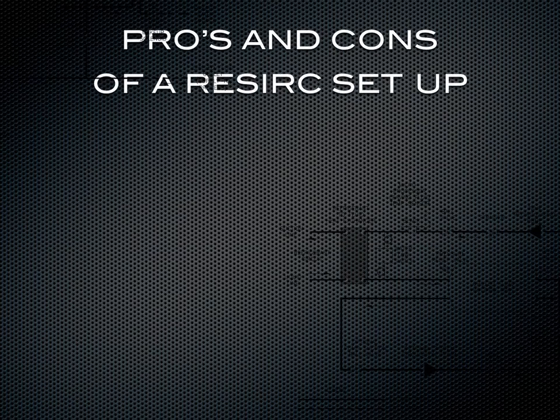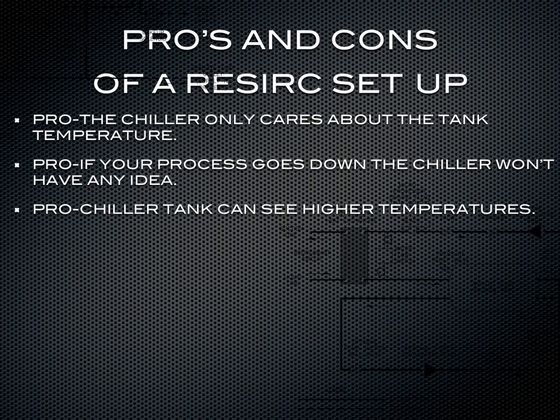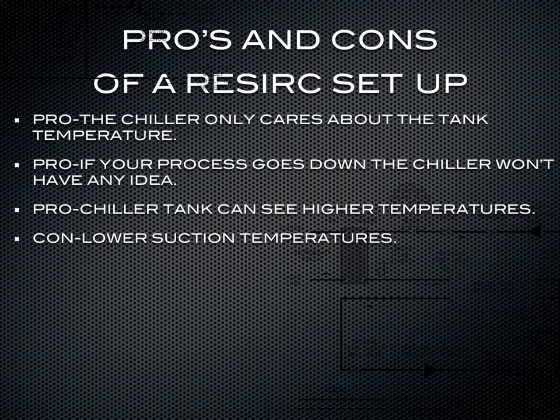The pros and cons of a recirc tank setup. One pro is that the chiller only cares about the tank temperature — if anything outside the chiller goes down or there are insufficient flow rates, the chiller has no idea and your refrigeration cycle will always keep going. Another pro is that you can handle higher fluid temperatures. A con is that the chiller is going to have lower suction temperatures. Suction temperature is the temperature of your refrigerant — the lower the refrigerant temperature, the less capacity on the chiller; the higher, the more capacity.